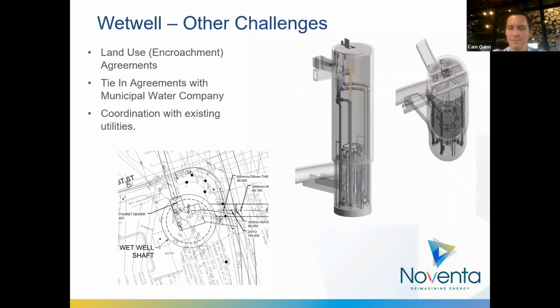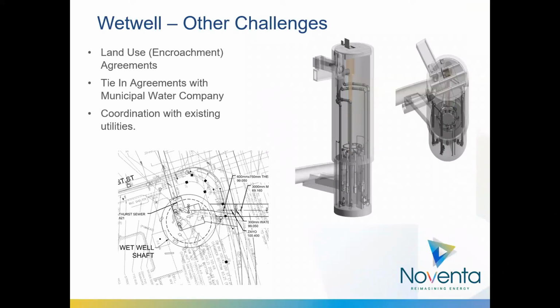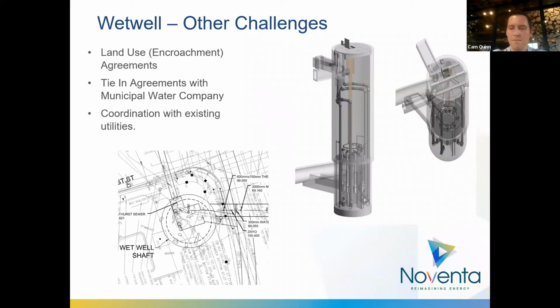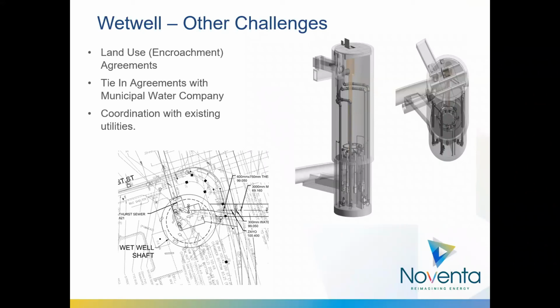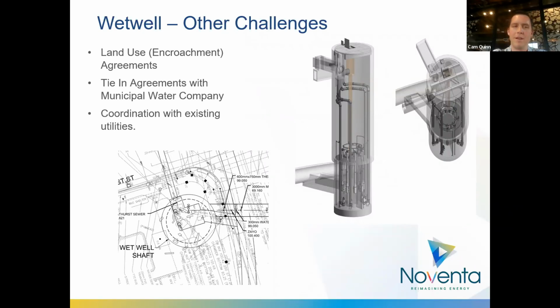Cam, wouldn't the temperatures you're able to produce depend somewhat on the heat pump technology as well? I think there are some industrial-type heat pumps, which we even provide, that can go upwards of 160 - dual stage heat pumps that can reach 160, even 180. So I don't think it's necessarily limited to 125, right? No, we do have some flex there - call 125 the design number.